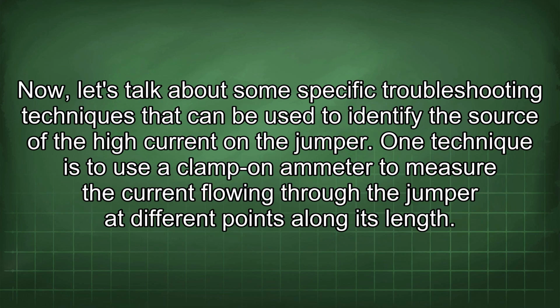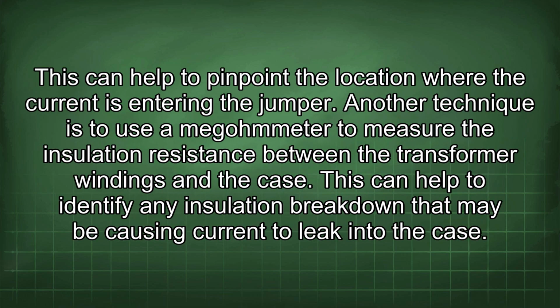Now let's talk about some specific troubleshooting techniques that can be used to identify the source of the high current in the jumper. One technique is to use a clamp-on ammeter to measure the current flowing through the jumper at different points along its length. This can help to pinpoint the location where the current is entering the jumper.